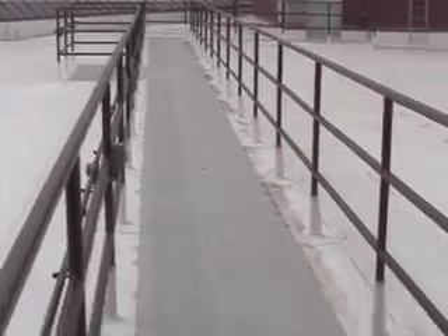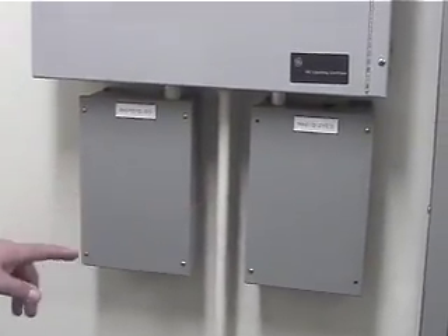So this is the walkway that's got the snow melt system underneath it. And then the sensor's right here, mounted on the handrail. So that picks up the snow and will give your enable to start the system. They had to put this in for egress because of the greenhouse, so they put the snow melt in to keep this path clear so you can get over to the other door if you have to.